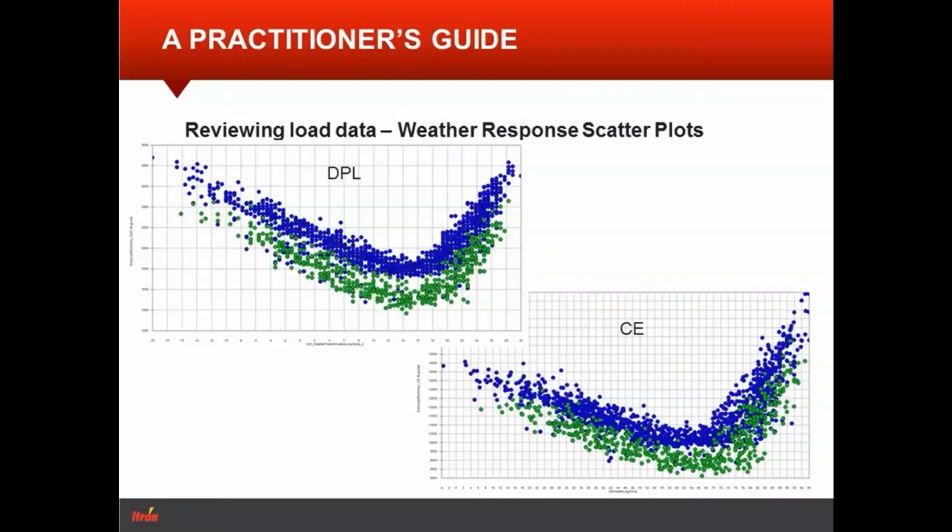And what this says is as temperatures vary, our energy goes up or down, depending on where we're at. What we notice is that the relationship between energy and temperature is nonlinear. And that's at the core of almost all power forecasting: we have this nonlinear response between loads and temperatures. And most of the techniques, and a lot of the literature, are about whether there are different statistical methods or frameworks that can handle this nonlinearity.